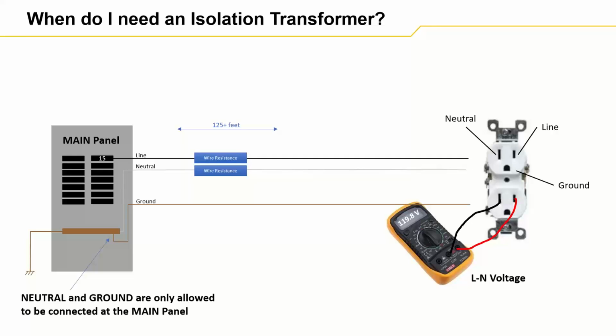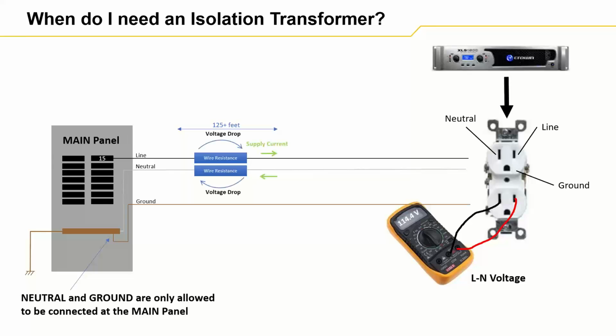However, the further your outlet is located from the main breaker panel, the more wire resistance buildup can occur. High current loads will pull current through the wire resistance and cause a voltage drop across the wire, which reduces the voltage at the output. At the same time, as the current returns down the neutral path, a similar voltage drop occurs across the impedance in that neutral wire, and that is what neutral to ground voltage is. And remember, neutral and ground are connected together, so theoretically that should be 0 there.